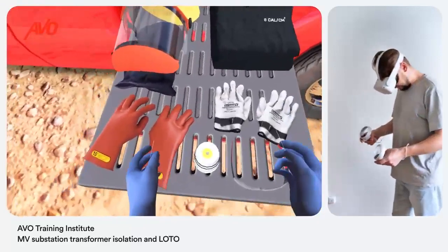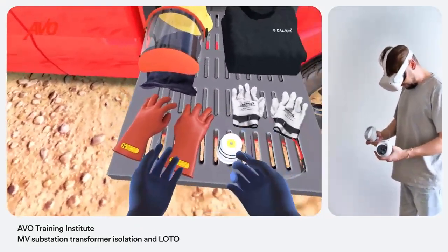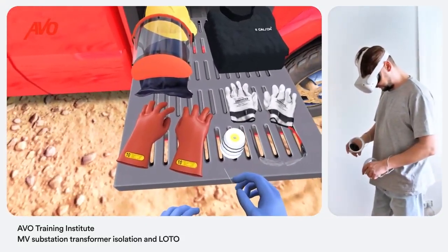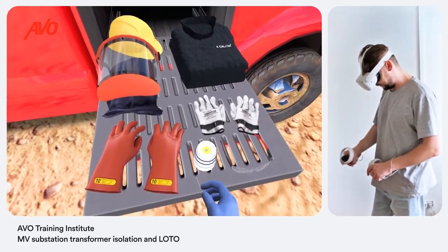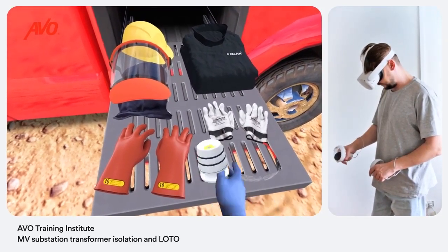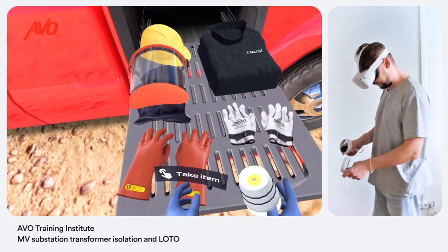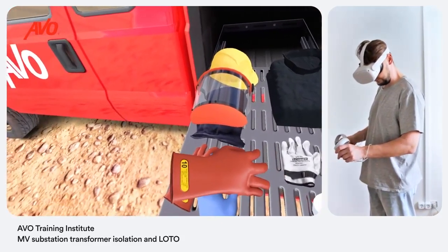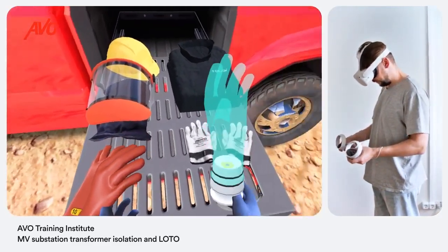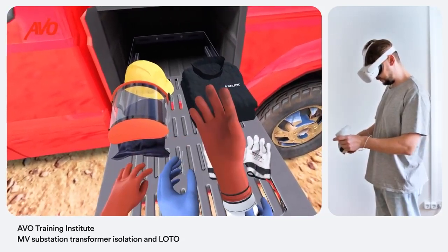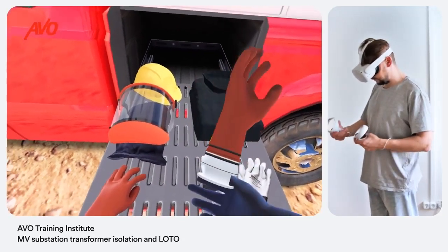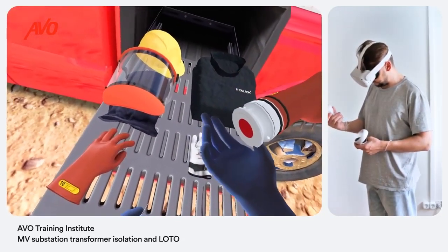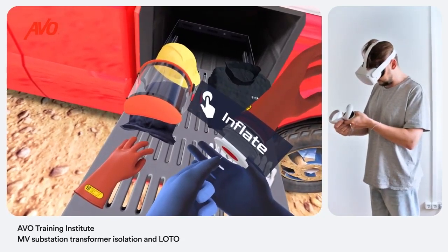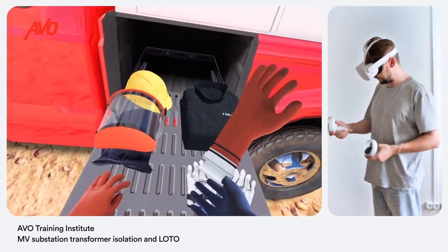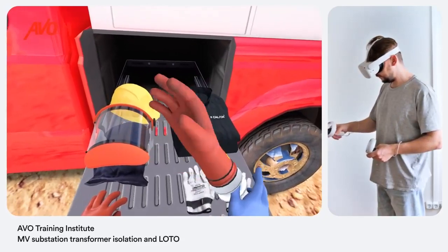OSHA requires you to perform a thorough inspection of your rubber gloves before each use. Let's perform an inflation test using a portable inflator. Slide the glove over the inflator and make sure the rubber O-rings are rolled onto the glove, which will prevent the glove from flying off when you inflate it. Inflate the glove using a push button at the bottom of the portable inflator. Hold the glove up to your ear and listen and feel for any air leaks.